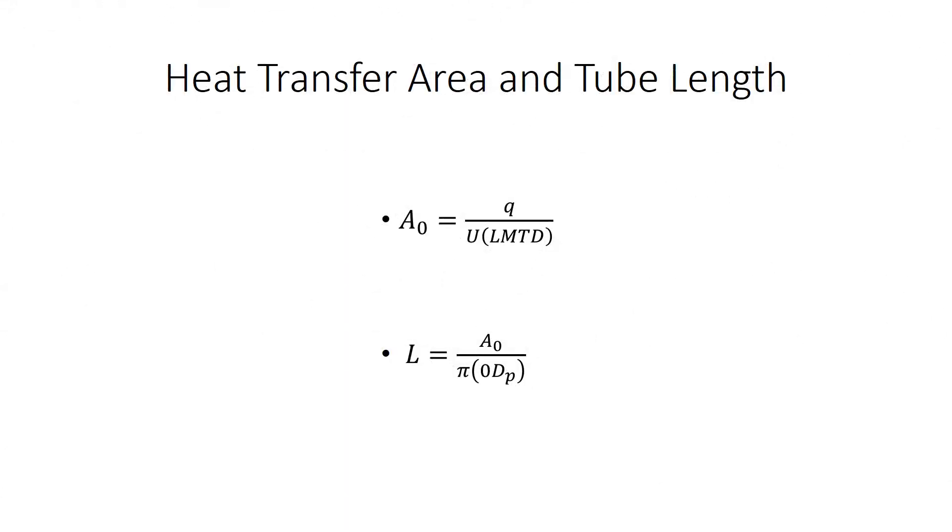Now to find the heat transfer area and the tube length, you can do that by doing simple algebra on the heat transfer equation to solve for area. With the area known, now you can find the length of the tube by dividing the area by pi times the outside diameter, and that will give you the length of the tube.